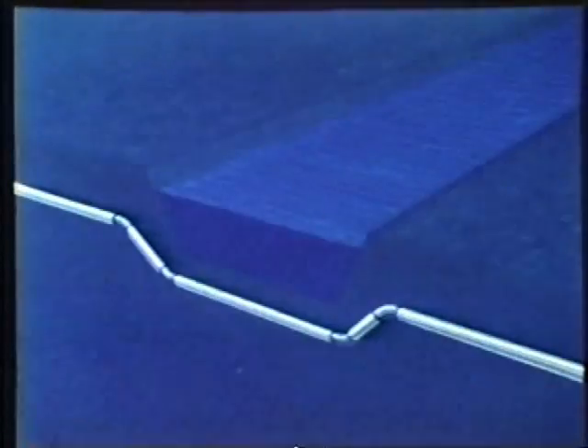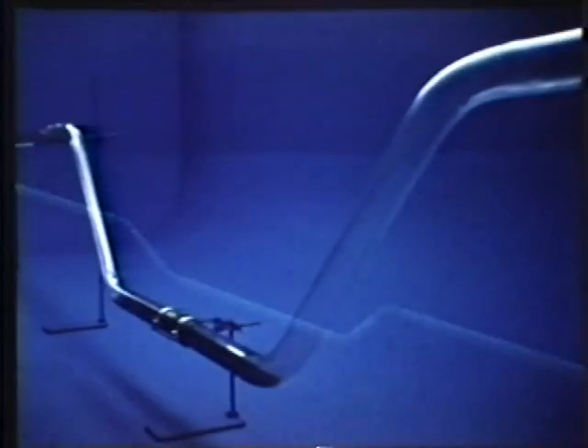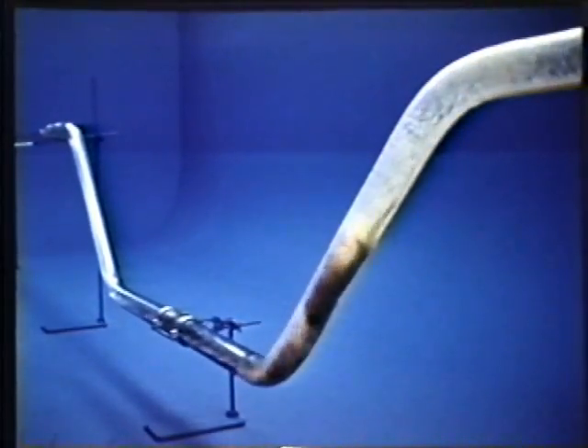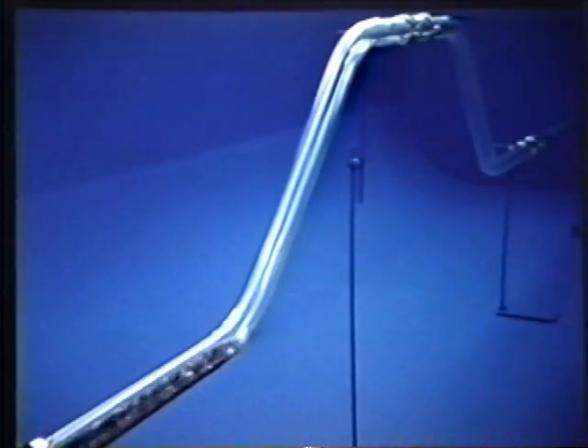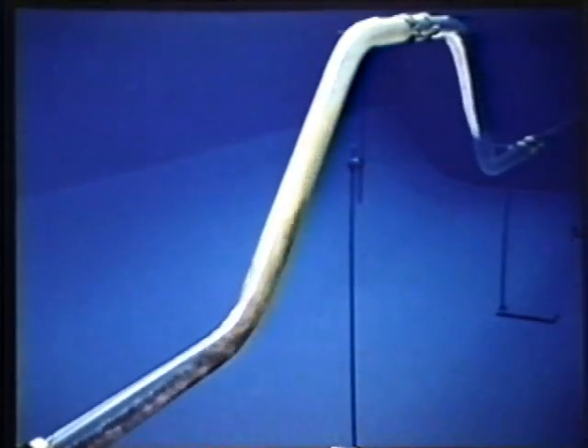In many places, the gas pipelines dive under rivers and canals. At low gas velocity, liquid can accumulate in these crossings. In autumn, when the gas offtake rises, the gas velocities increase, creating conditions likely to give rise to liquid being blown out of these crossings in slugs. At gas velocities in excess of about 4 meters per second, the condensate flows through the crossing without any difficulty. Liquid is also likely to accumulate upstream of dike crossings and can then be carried along by the gas when its velocity increases.